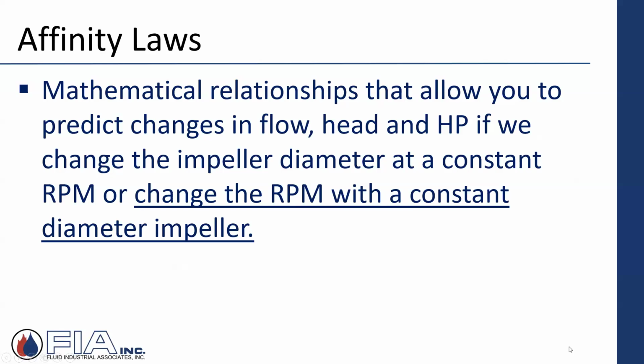So as you move into variable speed, it became the technology, VFD drives and all of that, taking an induction motor, maybe 60 hertz, 1750, 1800 RPM motors, or 3400, 3600 RPM motors. You start to apply this thing called the affinity laws, pump affinity laws. And I don't know that we touched on all of these last week, but they are mathematical relationships that allow you to predict not only the change in flow, but the change in head, and then the required horsepower, if we change either the impeller diameter, which we're not going to do, or change the RPM, which is our speed control. And that's what we're doing with variable speed. We're changing the speed.